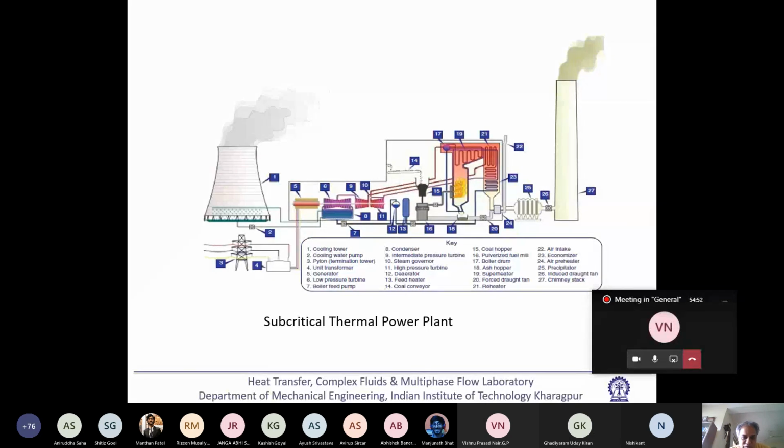And you yourself can decide, if we consider the flue gas path and the temperature is continuously changing, which heat exchange equipment will be kept where. Like at the lowest temperature, we should try to extract heat for air. At the highest temperature, we should try to extract heat for the superheater. Okay, so let us stop it here. We will again continue from this point. Thank you.